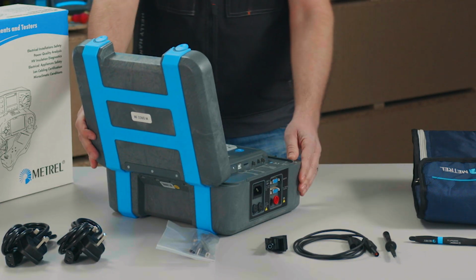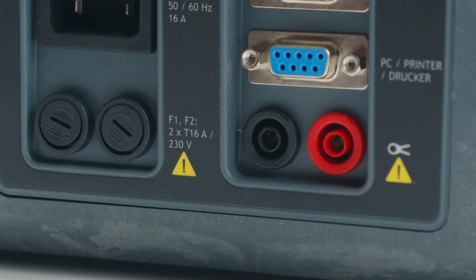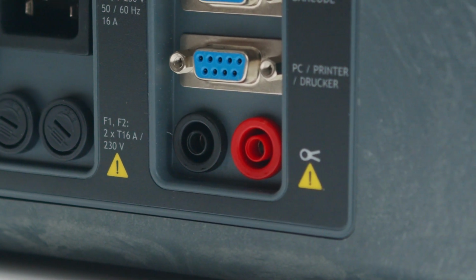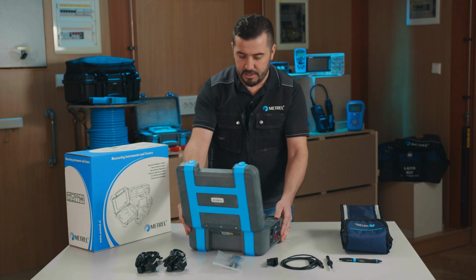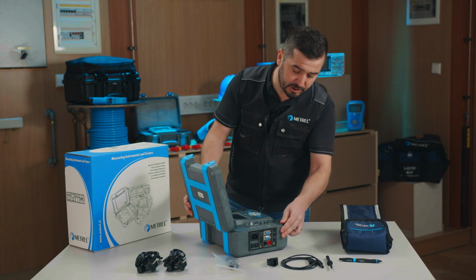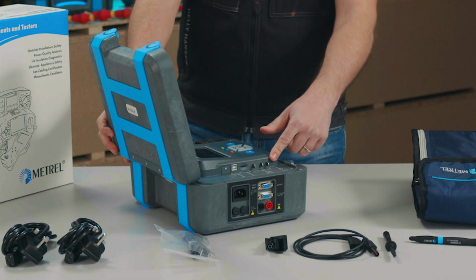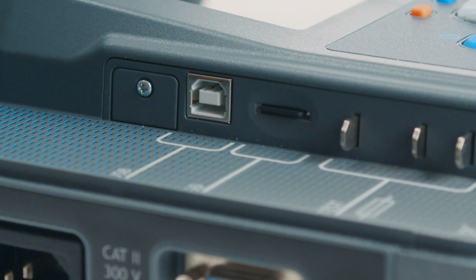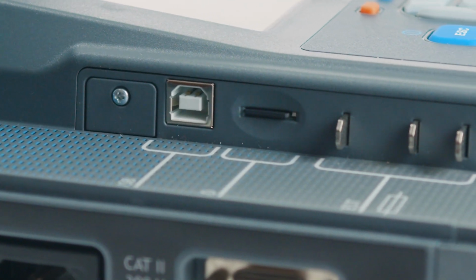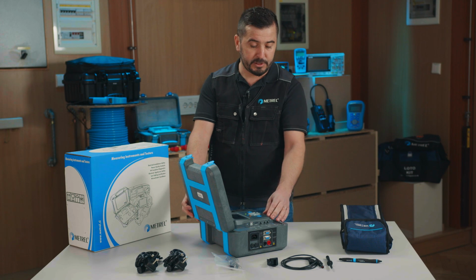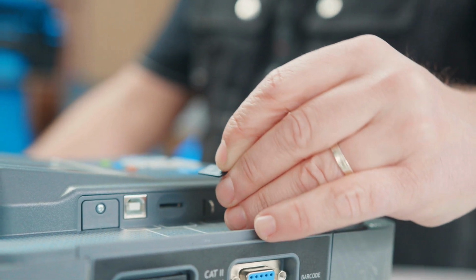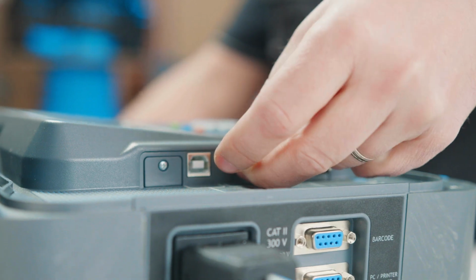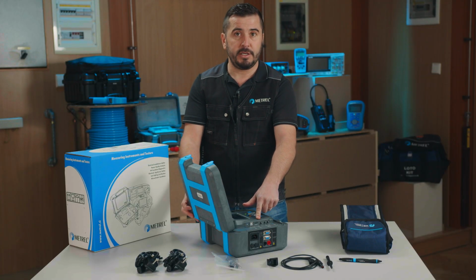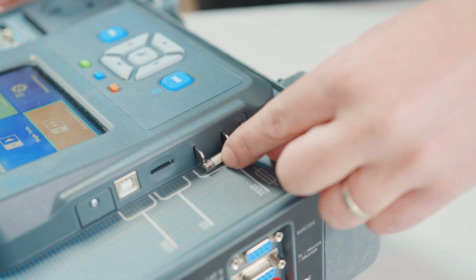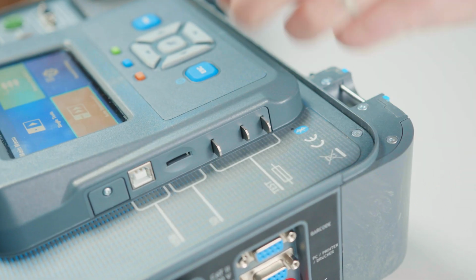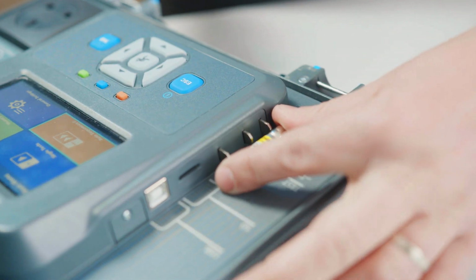Then we have two additional probe connectors for connecting very precise external leakage current clamps. We can also show here that we have a USB connector for connection of the download cable for transferring the data. Then we have a micro SD card slot equipped with a micro SD card, which comes with 8 GB inside. Then we have also test ports for checking fuses of different sizes.